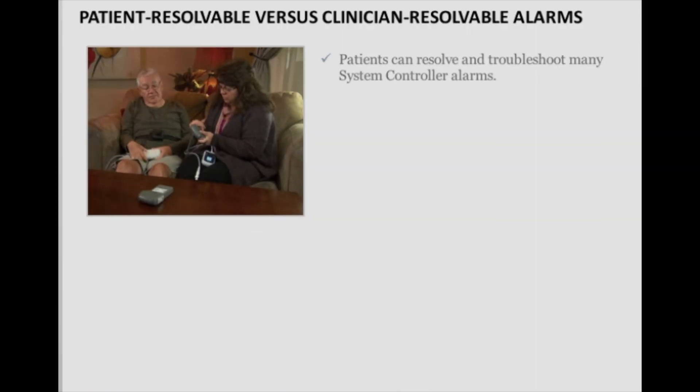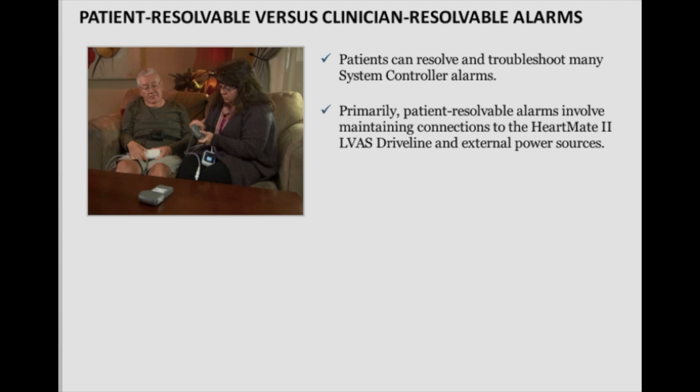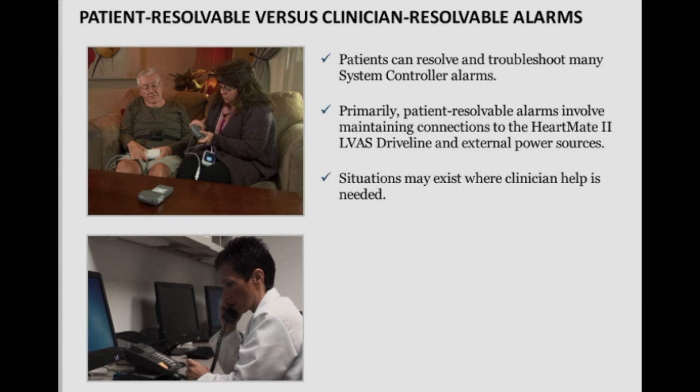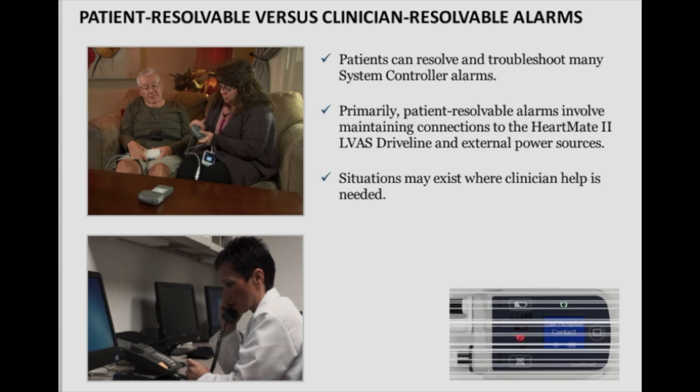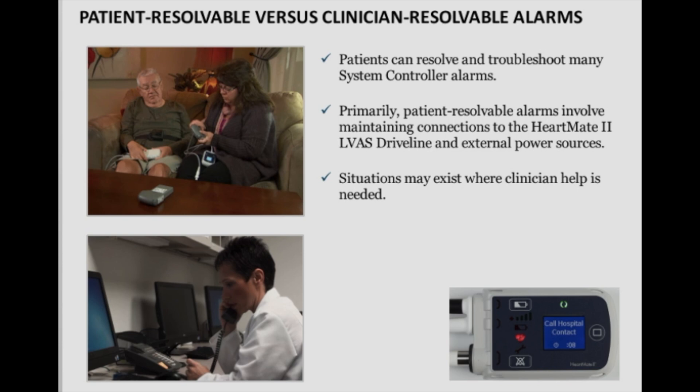Patients can resolve and troubleshoot many system controller alarms on their own, without clinician intervention. Primarily, patient-resolvable alarms involve maintaining connections to the HeartMate II LVAD driveline and external power sources. There are, however, situations where clinician help is needed. In these situations, a call hospital contact message appears on the information display screen.